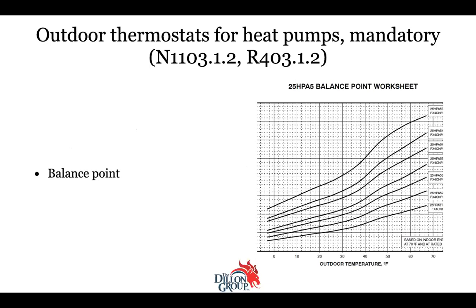So one of the first things I'd like to talk about, that a lot of things slide under the radar, is the outdoor thermostats for heat pumps. Now, this is a mandatory requirement. It's been in the code for a really long time. But most HVAC contractors don't know that on a heat pump, you can set that outdoor thermostat so that the electric resistance heat kicks in when the heat pump can't meet the load. It's not 40 degrees. Sometimes it's 12 degrees, like it is at my house. In fact, my heat pump has got a lot of stuff wrong with it, but there's a lot of stuff right. My heat pump can handle the heating load on my house all the way down till it gets 12 degrees outside before the electric resistance heat has to kick in.